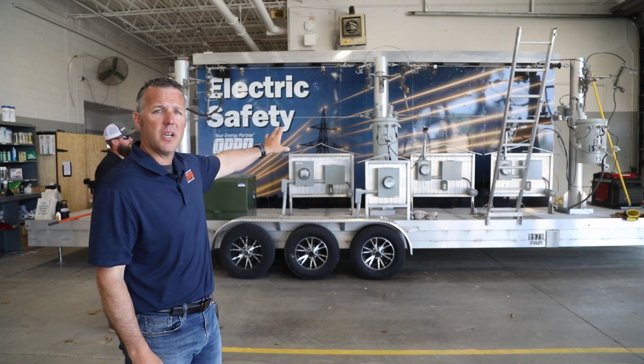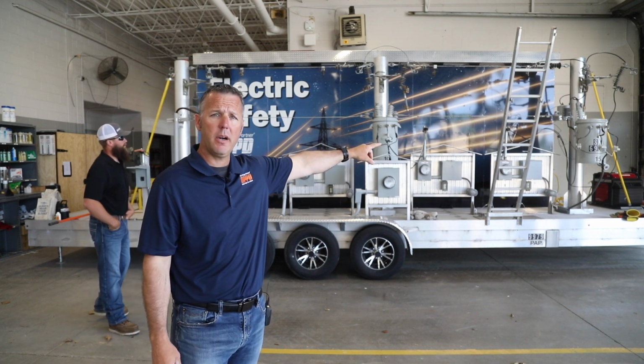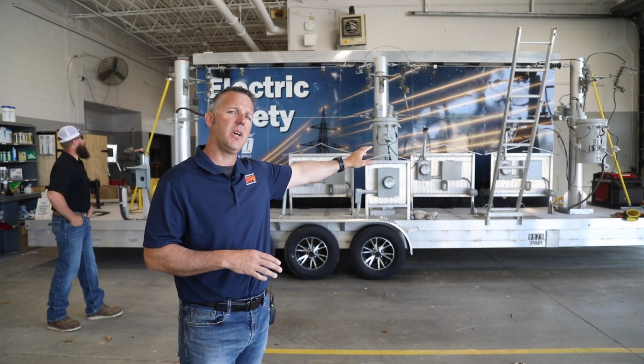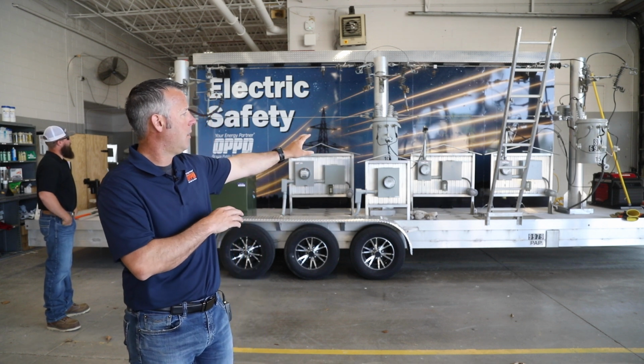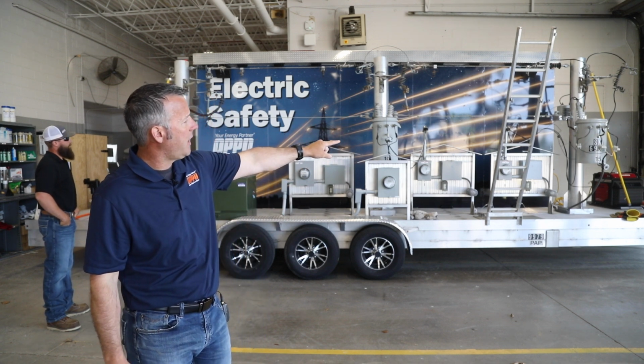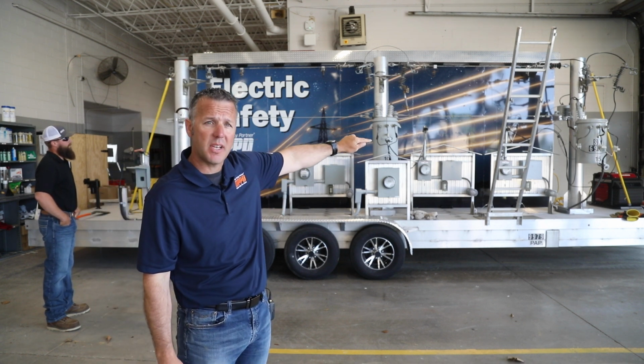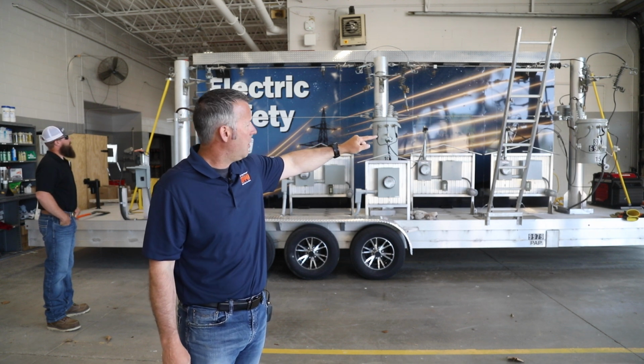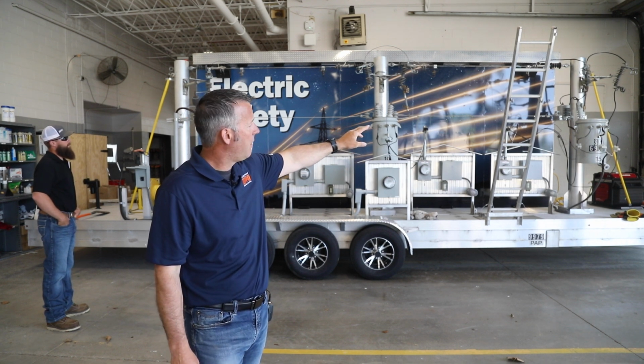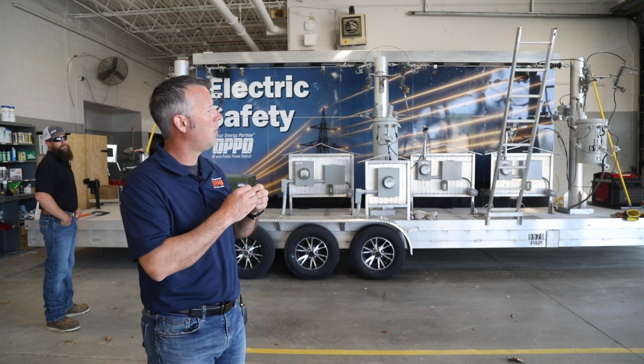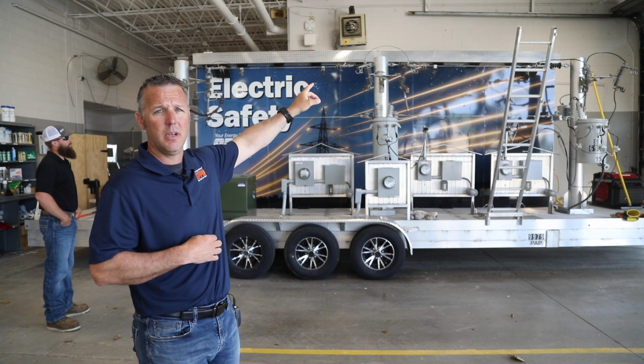So this trailer is going to be generated by a generator. Generally that's not how it's done, but for this scenario, this is what we do. So the generator actually is back feeding on our secondary side, so it's feeding in 120/240. The coils inside that transformer will step it up to 8,000.